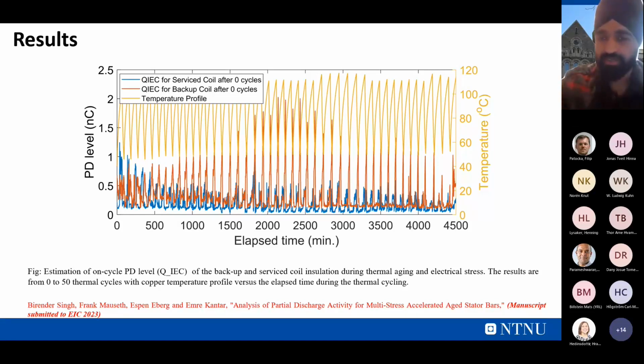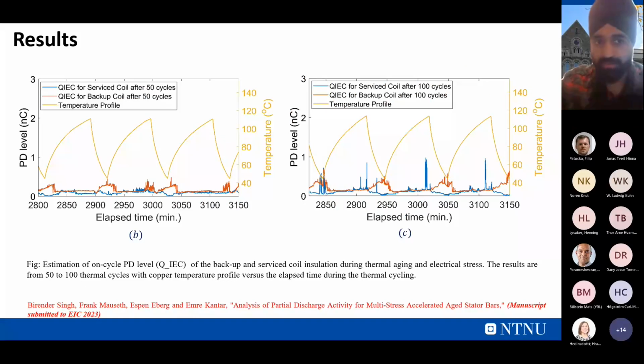These PD values are basically the amount of charge discharged. Usually the acceptable limits are 100 picocoulomb to 200 picocoulomb. But if it is near about 1 nanocoulomb, it is a huge amount of charge. In the initial cycles we observed this, but in later stages we found that it starts disappearing. After 50 cycles, we found that these charges disappear for the backup coil and also the service coil. This kind of behavior is maintained till 100 cycles.